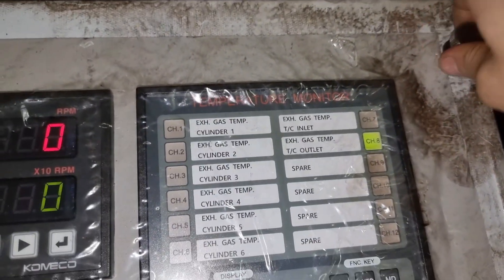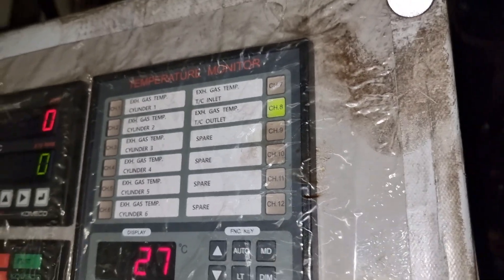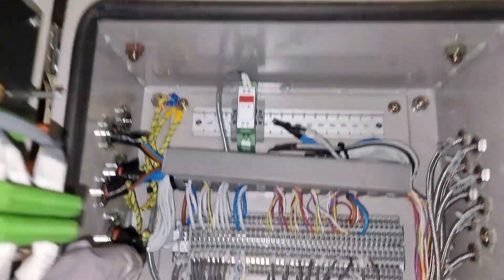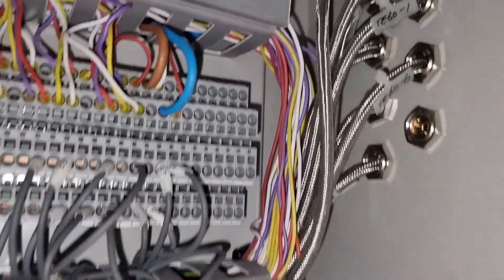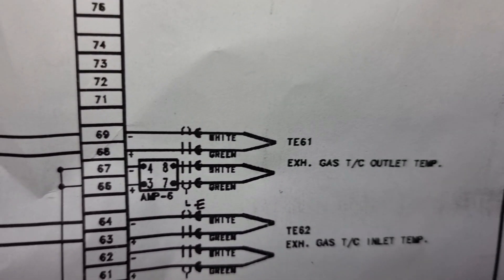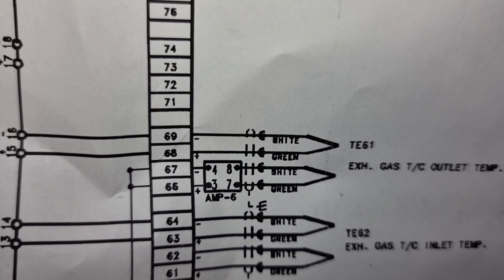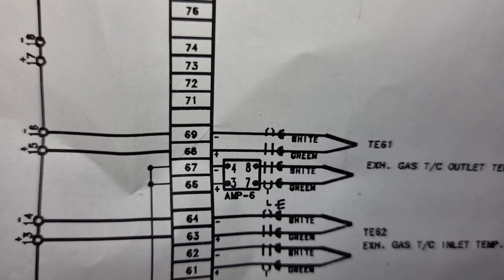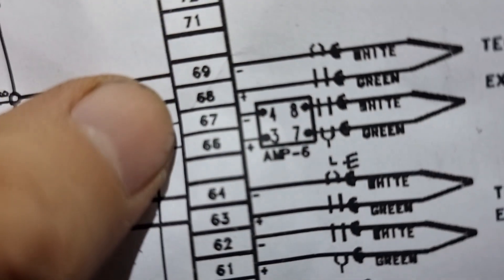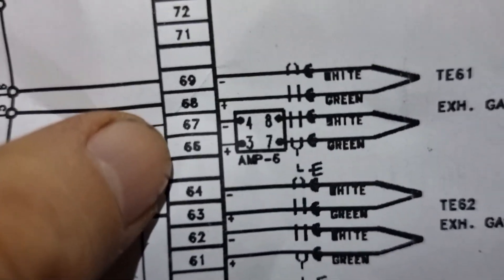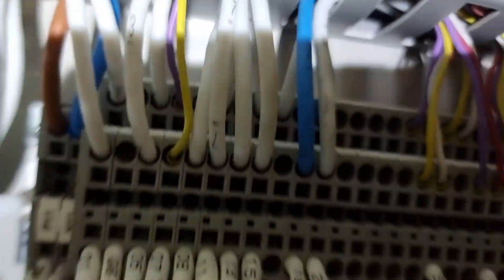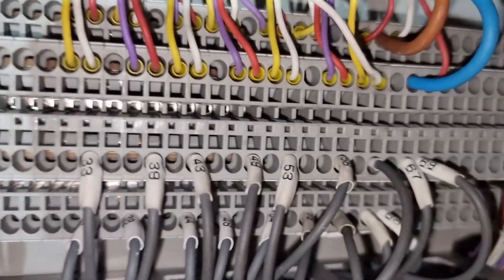As per the manual, the four wires are connected to number 68, 69, but the other pair is connected to an amplifier before it goes to number 66 and 67 terminal. So let's locate first the number 68 and 69 as this is not the one that's connected to the amplifier.